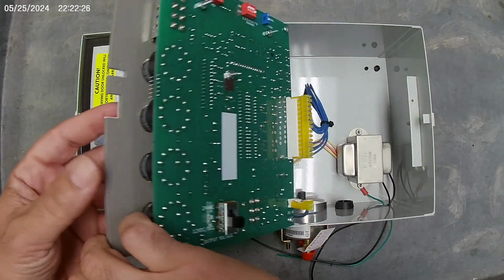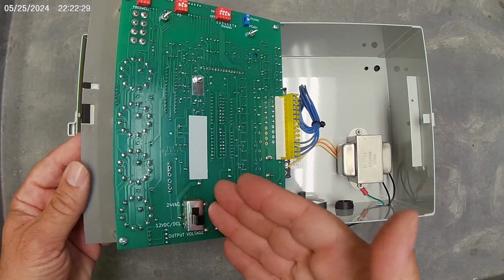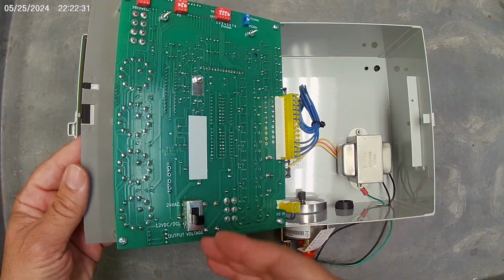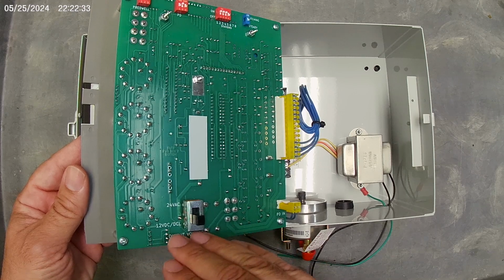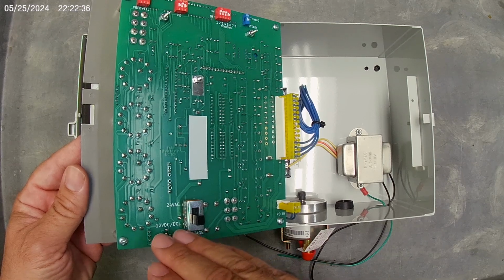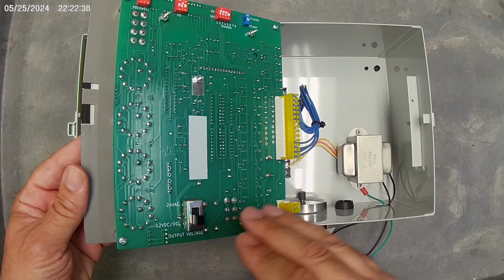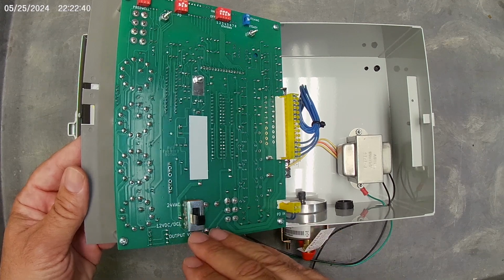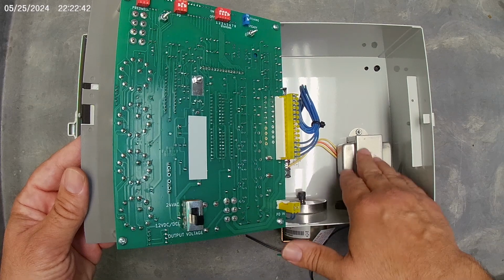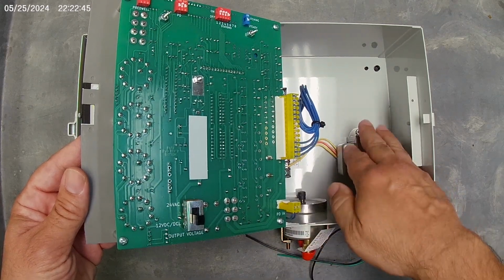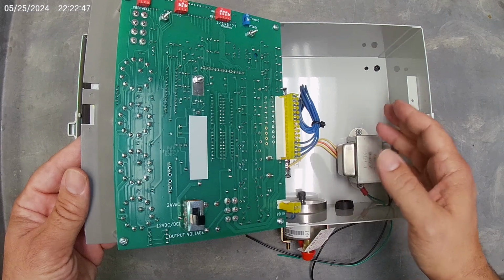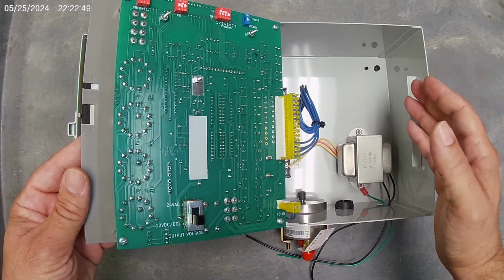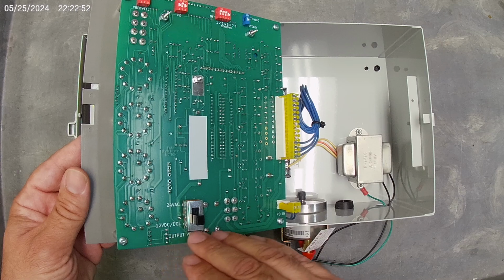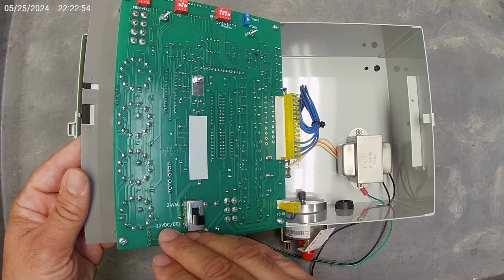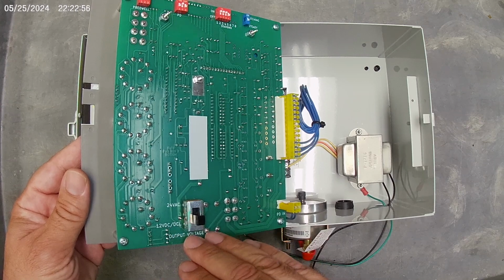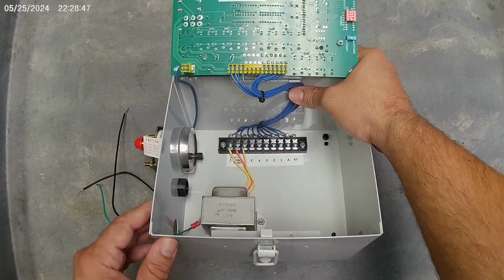In initial setup, you're going to want to determine which solenoids you have. These controllers can operate either 12-volt DC or 24-volt AC latching and 12-volt latching, with the provided transformer. If you do not use the provided transformer and are operating from either a battery or a solar system, you will only be able to operate in the 12-volt DC or preferably 12-volt DC latching mode to conserve power. Wiring of the system is straightforward.